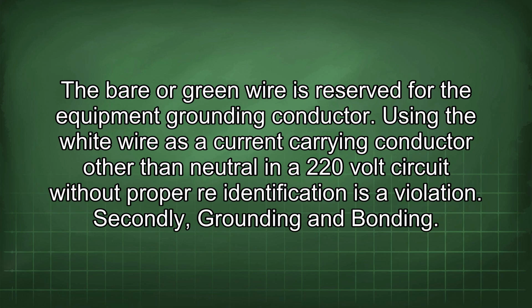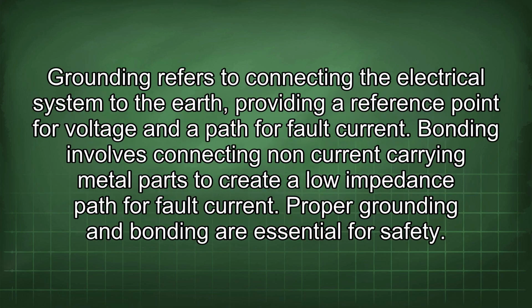Using the white wire as a current-carrying conductor other than neutral in a 220-volt circuit without proper re-identification is a violation. Secondly, grounding and bonding. Grounding refers to connecting the electrical system to the earth, providing a reference point for voltage and a path for fault current. Bonding involves connecting non-current carrying metal parts to create a low impedance path for fault current. Proper grounding and bonding are essential for safety.